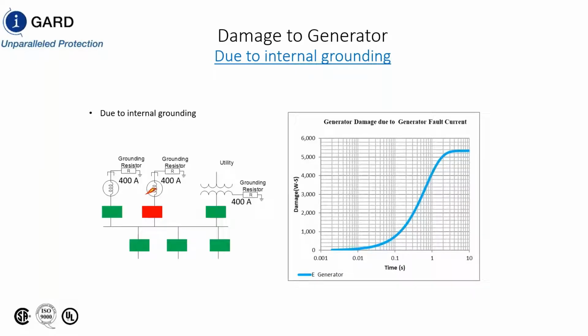So the damage that occurs to the stator fault winding after the breaker has opened is 5,333 watt-seconds of damage. And that's because just because we've opened up this breaker doesn't necessarily mean we've stopped generating power. That generator is going to continue producing power until it winds down. And you can see here that the maximum fault current occurs around the 3 or 4 second mark. So if it takes a long time to wind down, then it's going to increase that damage.